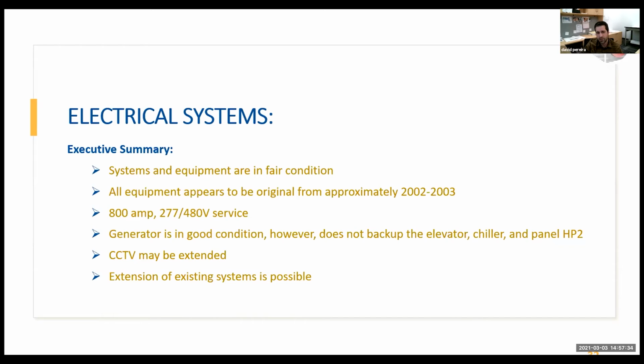Generator's in good condition. However, there were certain items - and I don't know if it was problematic, and I'd like to hear from the owner - that didn't back up the elevator, the chiller, or anything on panel HP2. I don't know if that's been problematic or if things seem okay when power is out. The CCTV system, I need a little more information on to see if it could just be extended with cameras added. Seems like some upgrades have been made, so essentially extension of most systems is possible for this renovation project.